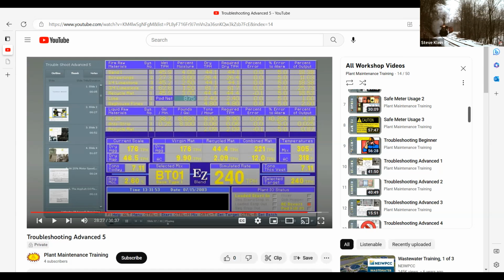That little tachometer on there has a little glass disc on it, and it'll tell you how many pulses per revolution, like 12,000 or 1,000 little individual lines going past the sensor. That signal train is coming in as a frequency. The computer's set up to tell the frequency of how many times it went around in a minute or in an hour. Each revolution is supposed to weigh so much, and I'm correcting for temperature. That's how the magic happens, that it tells you so many tons per hour.